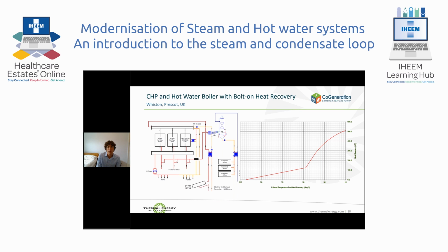This is the heat recovery curve here. You can see we're taking heat out of the existing CHP heat recovery systems at just over 100 degrees C, and the dew point here is slightly below. This is below what we see in a natural gas-fired boiler due to the additional excess air we have in a CHP system. Here it's just below 50 degrees C. The system recovered from the hot water boilers and the CHP, as I said, delivering that heat to 3 domestic hot water calorifiers and also preheating the hot water hydronic return loop.